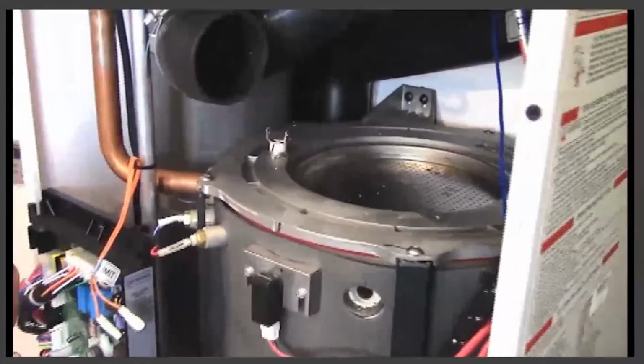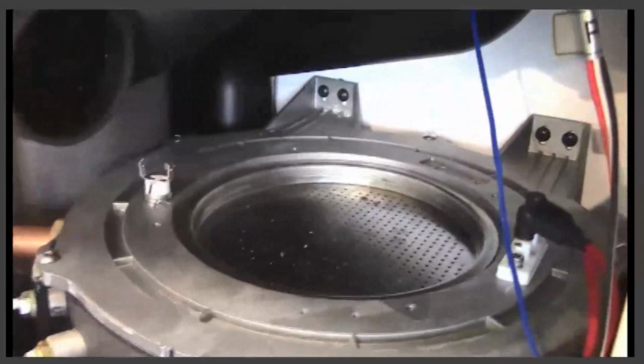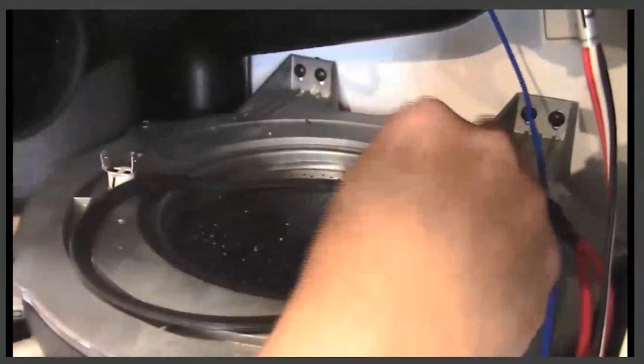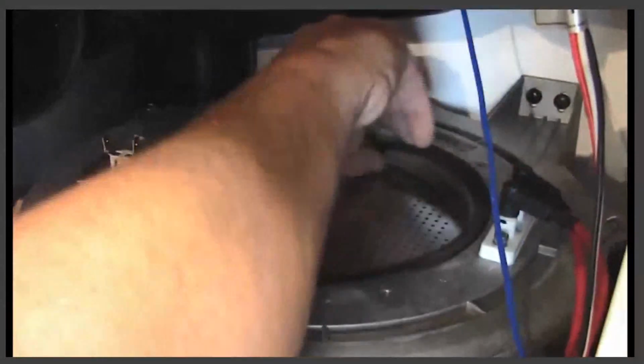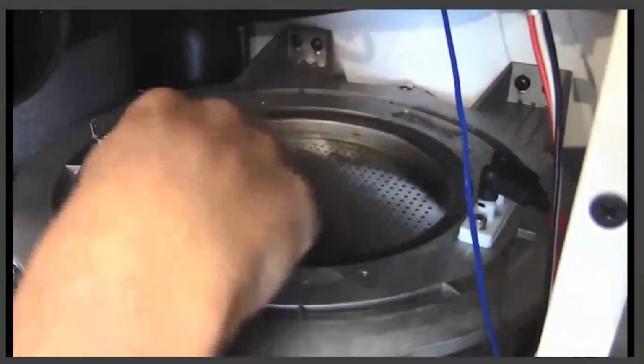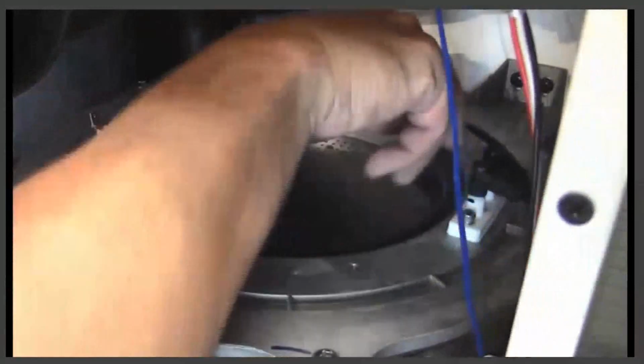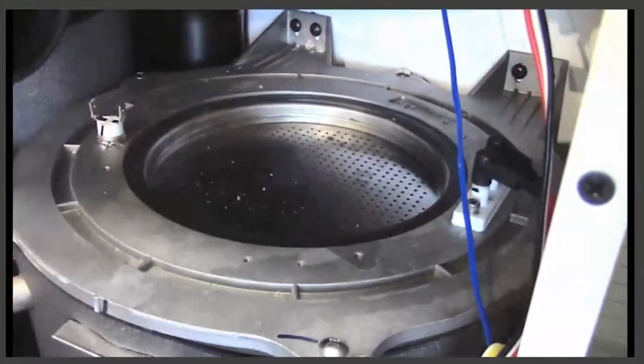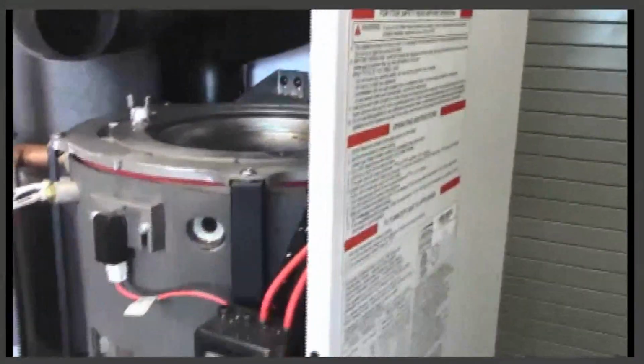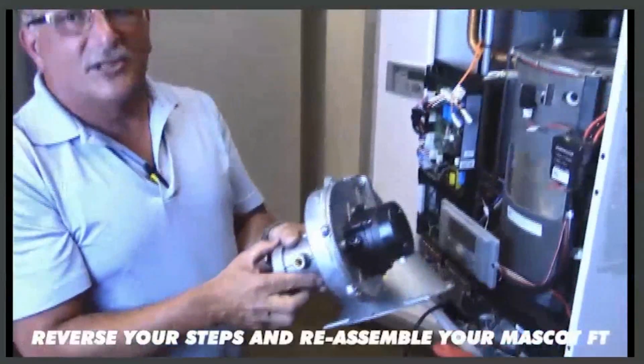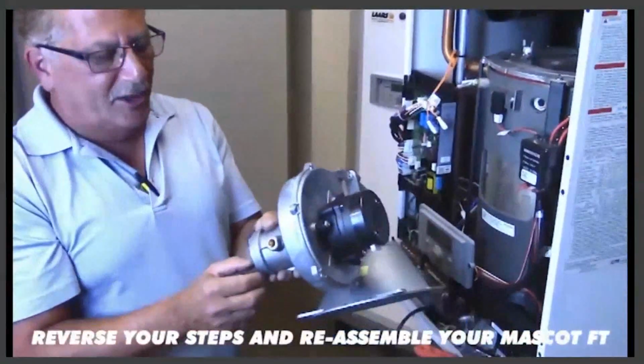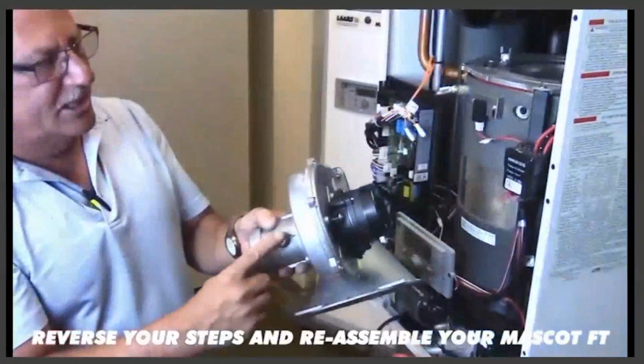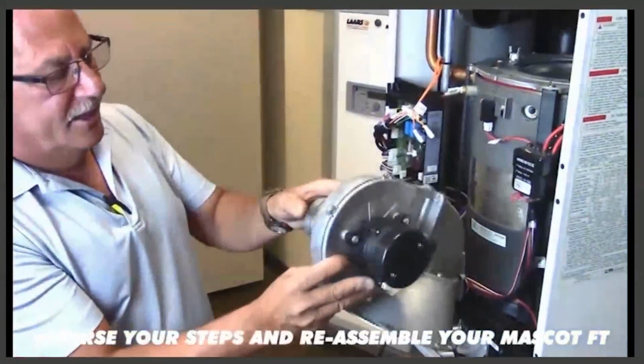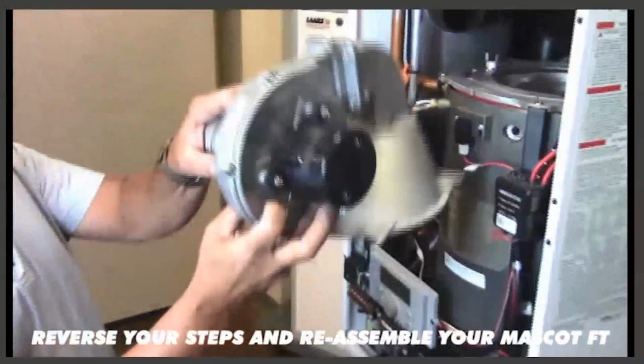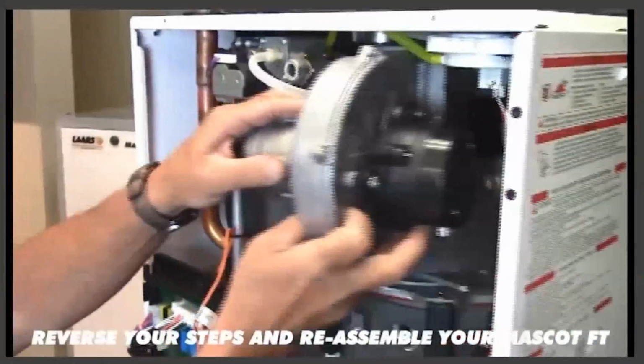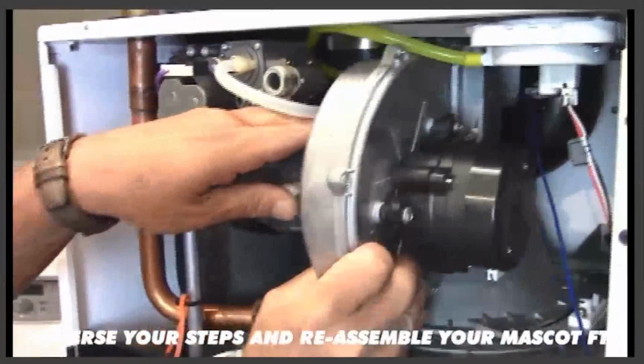Installation of the gasket. After inspection of that gasket and replacement if necessary, make sure that gasket, as was said before, is in its proper place. And we can now go ahead and put the burner housing back together. Reversing our steps and reinstalling the burner housing itself, please keep in mind that orifice. So I find it best to just hold the orifice in place while getting the housing back onto the top of the heat exchanger.